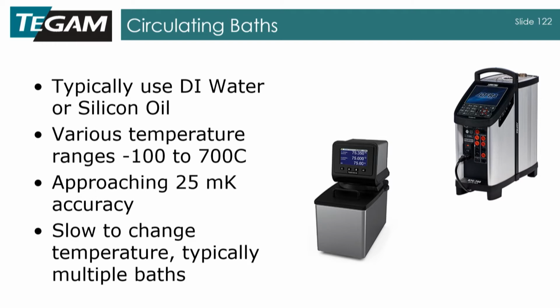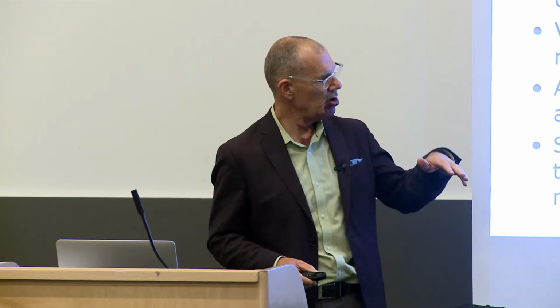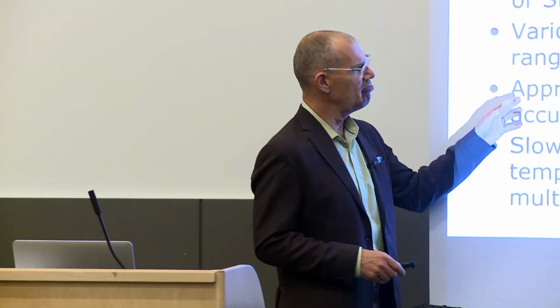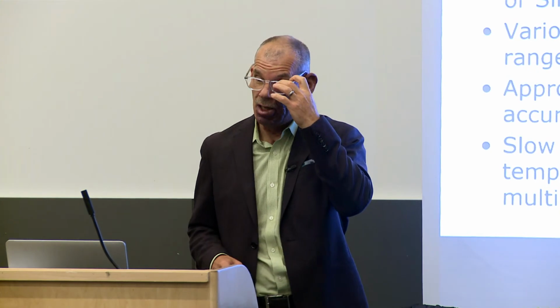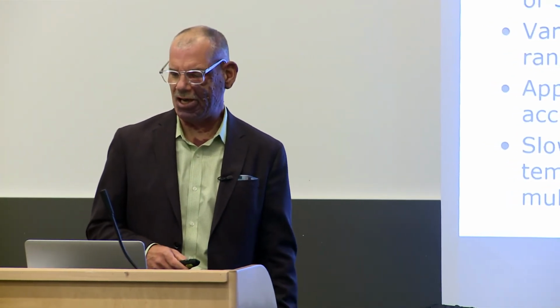But the key for most baths is not the accuracy of the control system. What you want is stability, how stable the bath is, because you're going to discipline it with an external sensor. When we upgraded our lab's accuracy, we bought a bath with pretty decent stability, but we used an SPRT to bring it down in uncertainty. With our own SPRT and an external long scale voltmeter, that's a temperature scanner, we could get to 6 millikelvin, which is pretty decent. And we're using that to pattern some of our own RTDs and sensors that we're putting into products.